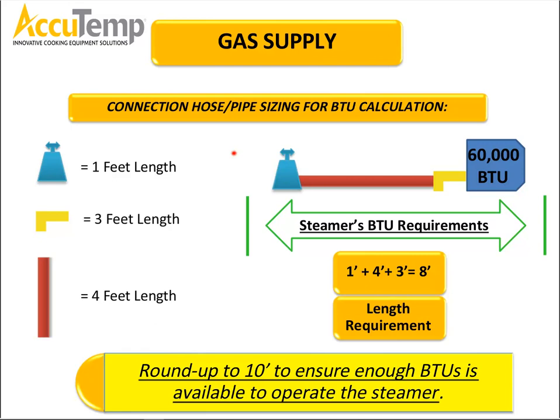So here's a little basic example. We've got a fitting at 1 foot, an extended 90-degree at 3 feet, then a 4-foot pipe or gas line. So this is really quick. We add them up, we've got 8, and then of course let's go to 10. And if it's 1 inch, remember 10 feet can support over 600,000 BTUs. So obviously, if we can support 600,000 BTUs, your steamer will run because the steamer is only rated for 60,000.